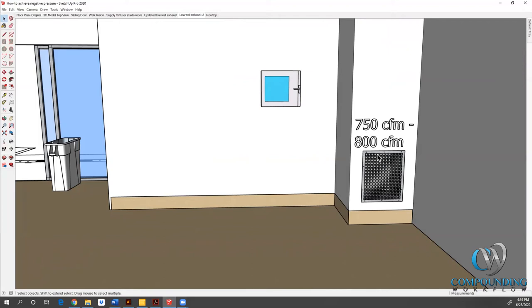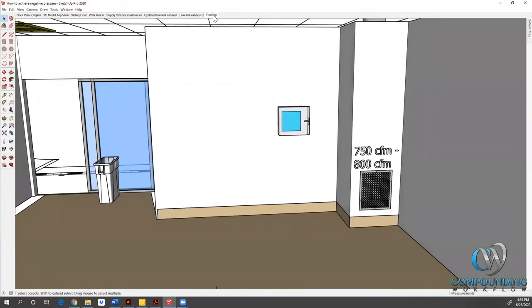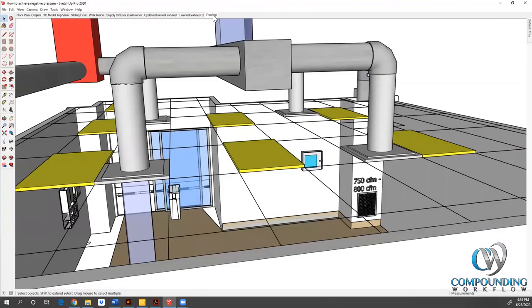Then in each opposing corner, I've got a fairly large low wall exhaust grate here. There's ductwork hiding behind this drywall chase or FRP or whatever the surface is, and then I'll show you how those are connected. I don't typically like to move more than 500 to 800 CFM through a low wall exhaust. I don't like to get up to a thousand because you'll find sometimes if the ductwork is not properly sized or you're moving air too fast, the low walls will actually start to whistle. Nobody wants to work in a compounding room where your walls are whistling. So you can see in each of the corners, both opposing corners, we're going to try to balance this. It may not always balance out to be an even 50-50, but that is the design goal.